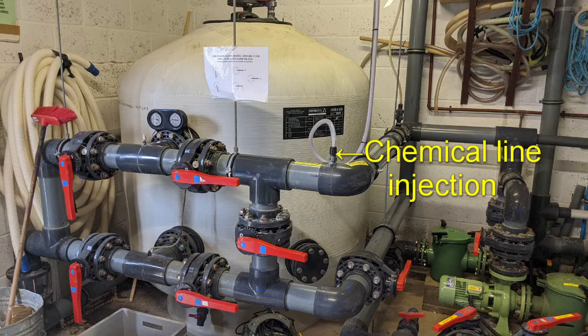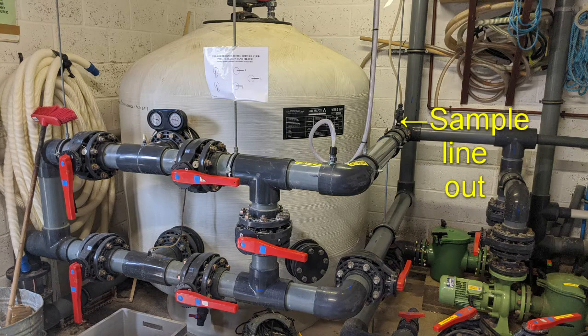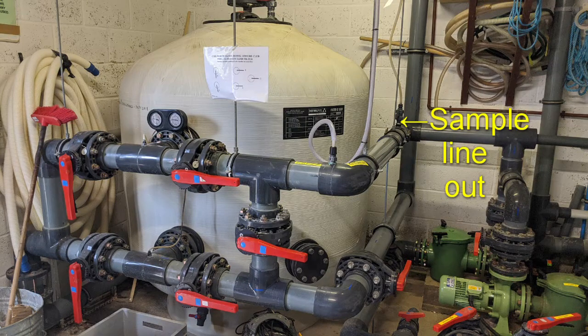But along the way, on the pipework between the circulation pumps and the filtration system, you'll probably see chemical feed lines or sample feed lines coming into or being taken from the main pipework. The first thing you're likely to see coming off the main circulation pipework between the circulation pumps and the filters, pretty soon after the water's gone through the circulation pumps, is the sample water that is taken to the automatic monitoring equipment. Follow that along. When you've identified it, follow it, trace it back and see where it's going.